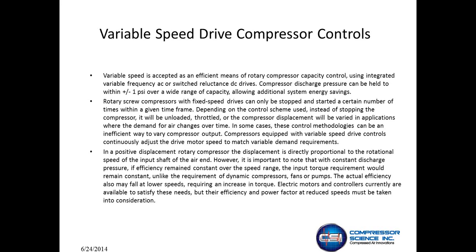Where you get into problems is, again, you need to match your variable speed drive to the demand. You want to be in the sweet spot, 50 to 80%. When you start getting below that, you start to lose efficiency across the air end. You start to lose efficiency across the rotor. So it's not as efficient if it's not applied in the right application. So you really have to look at variable speed drive as not being the best solution to every application. It has to be applied as a trim machine or as a standalone machine within the right capacity range.